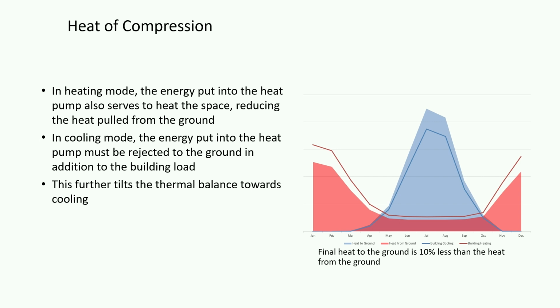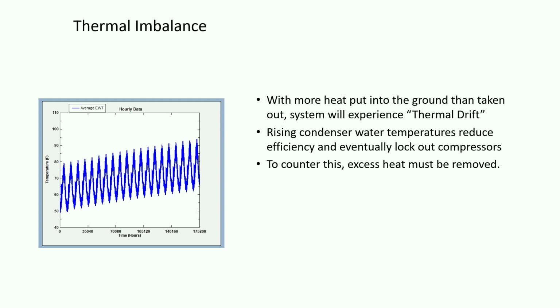So that's how we get from a building where we said before we had about 40% more heating than cooling. Once you factor in this heat of compression, in this particular example, now you actually have 10% more total cooling over the course of your year than you have heating. Why does this matter at all? As we all know, our ground is a thermal reservoir. If every single year you are dumping in more heat to the ground than you're taking out, you're going to slowly see the temperature of the water that you're pulling out of the ground rise year over year.